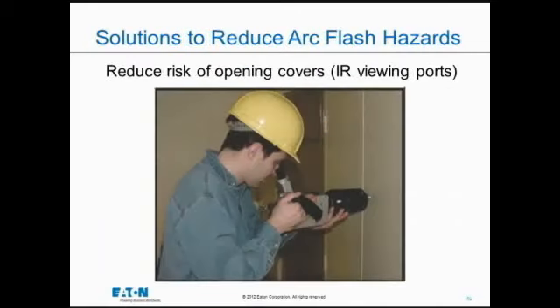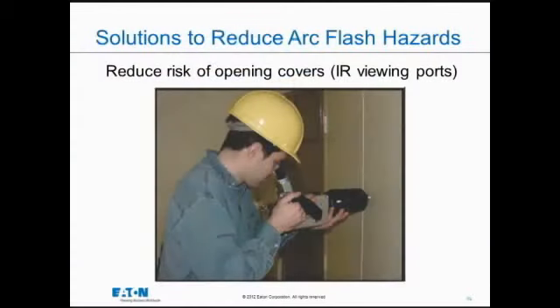Using windows that are transparent to infrared radiation and not having to open doors and covers is a huge increase in safety, a reduction of risk. We've had a lot of stories over the last few years of people being injured opening up doors or covers, and one of the tasks that we do quite frequently is infrared scan. We can't see through the steel door. We need to get that door open or that cover off to get access to those parts that are still energized, because we want to have them energized to pick up the hot spots. And so infrared, reducing risk with covers, is a good idea.